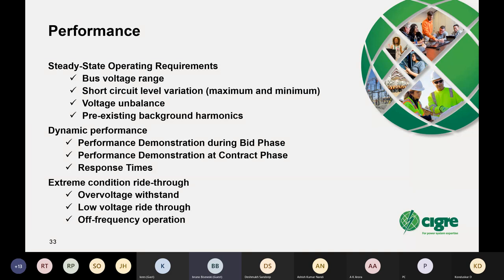Typically, you would have, let's say, a preliminary performance demonstration during the bid phase, followed by a more detailed performance demonstration during the contract phase. You might include recovery response times for step changes, as well as fault recovery times from DC faults or after AC faults. Also, you need to specify extreme condition ride-through or withstand requirements. Those would include overvoltage withstand, low voltage ride-through requirements, and off-frequency operation requirements.